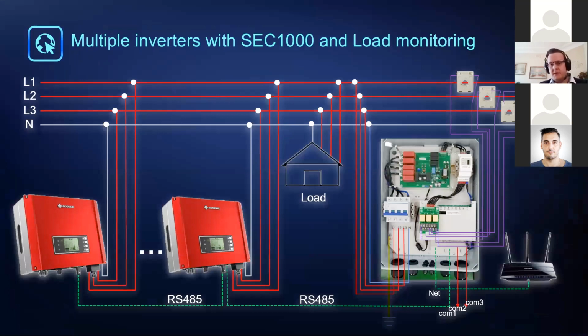For our multiple inverters with the SEC 1000, you'll see you can use your own custom CTs. The SEC 1000 has an internal breaker, so we just connect our lines 1, 2, and 3 and neutral up to this, and we can connect our CTs below. In the SEC 1000, we've got full Wi-Fi and LAN as well.